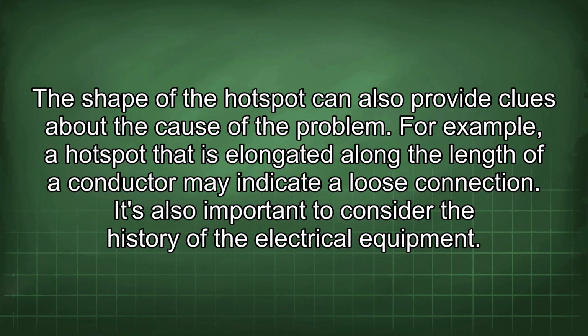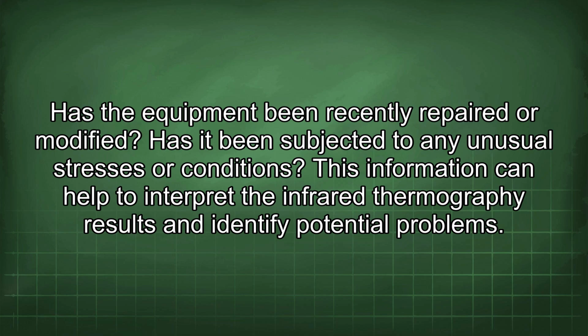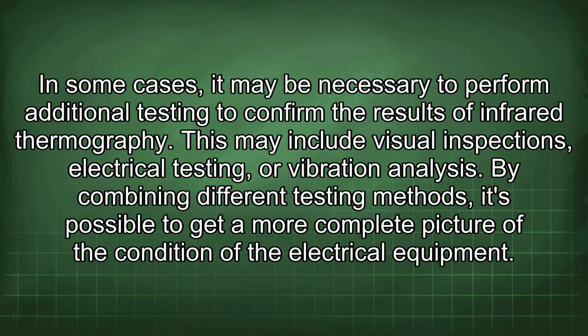It's also important to consider the history of the electrical equipment. Has the equipment been recently repaired or modified? Has it been subjected to any unusual stresses or conditions? This information can help to interpret the infrared thermography results and identify potential problems. In some cases, it may be necessary to perform additional testing to confirm the results of infrared thermography. This may include visual inspections, electrical testing, or vibration analysis. By combining different testing methods, it's possible to get a more complete picture of the condition of the electrical equipment.